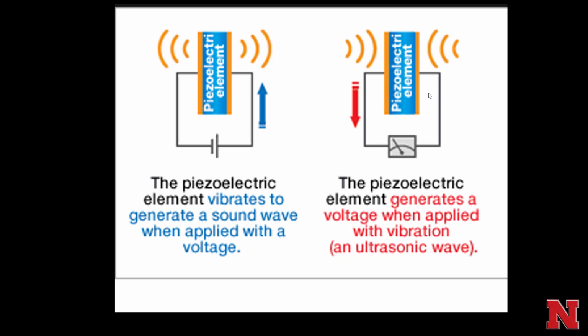A piezoelectric element, the basic functional part of a transducer, vibrates to generate a sound wave when a voltage is applied, and generates a voltage when a vibration is applied. The same basic concept sends out the sound wave and listens to the returning echo, and through computer processing, those electrical impulses form an image on a screen.